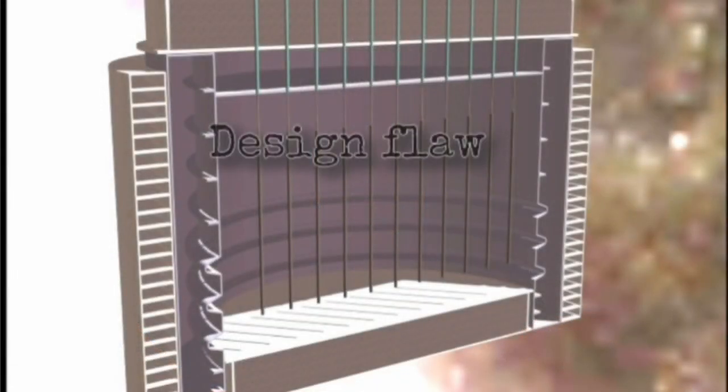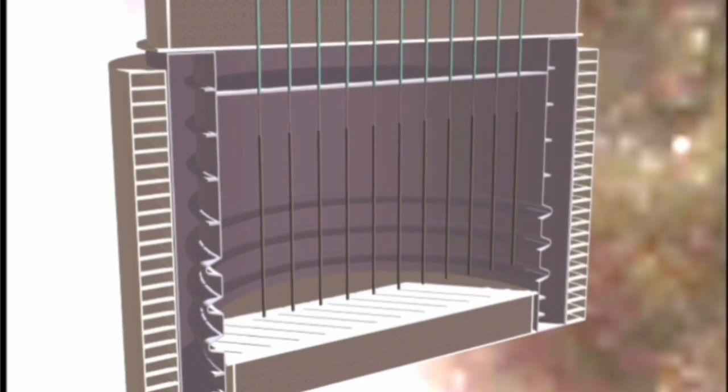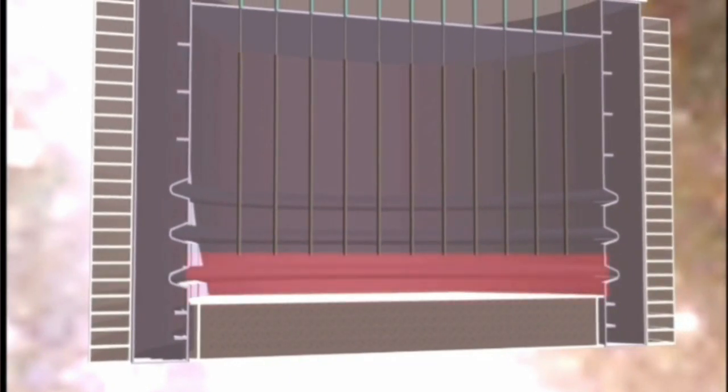You guys must be wondering why the explosion occurred. It was a result of a design error called the tip effect, causing a momentary power spike precisely when the control rods were supposed to kill reactivity. The graphite displacers did not extend all the way down to the floor of the reactor. The lowest 1.25 meters was cut short to equalize fuel burn as there was lack of space below. The base of the reactor was the place where everything went to a mess.